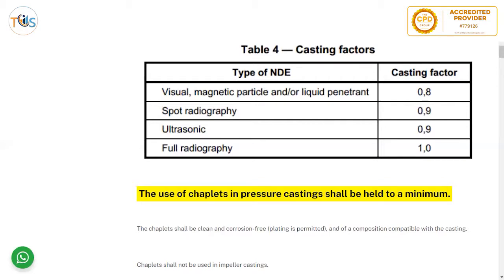If you perform only a visual, magnetic particle, or liquid penetrant inspection, you get a casting factor EC of 0.8, used for determining minimum thickness considering pressure. Spot radiography or ultrasonic testing gives EC of 0.9. Full radiography gives EC of 1.0, meaning the full casting factor can be utilized because you are certain no defect is present. The casting factor increases with the level of certainty of your examination.